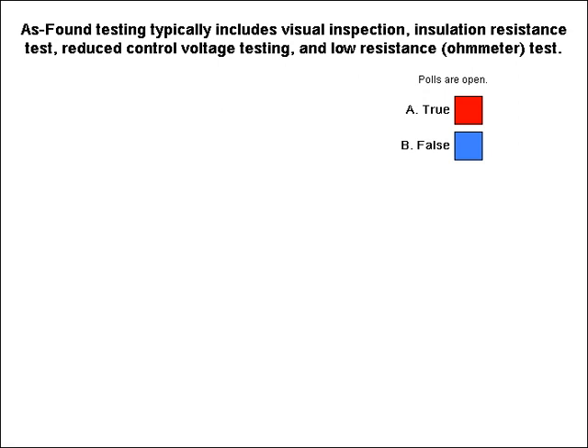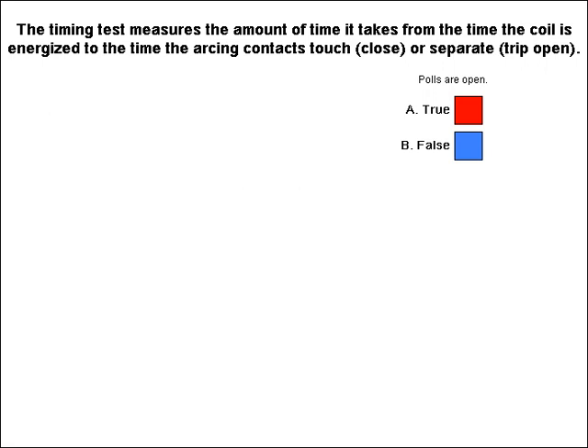Okay, I believe this is the last question. Timing test measures the amount of time it takes from the time the coil is energized to the time the arcing contact touch or close or separate, trip open. So the timing test measures the amount of time it takes from the time the coil is energized to the time the arcing contact either during close touches or when tripping open, the arcing contact separates or opens.